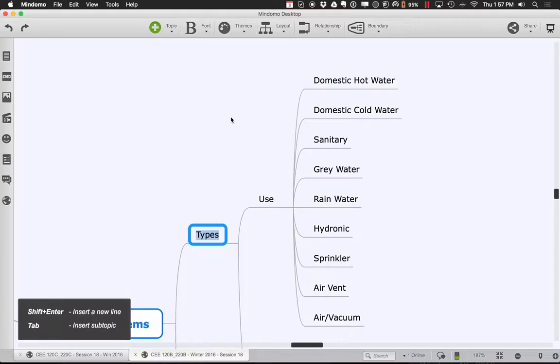Gray water systems we'll talk about today — we could also be collecting rainwater and using it for irrigation or landscaping. Hydronic water tends to be a separate system where hot or cold water runs through radiators or into the heating and cooling system. Sprinkler water is another separate plumbing system — sprinkler piping tends to be very high pressure because you need a very big burst of water volume when necessary. If we had the same pressure needed for sprinklers on a cold water tap, every time it turned on it would blast you.